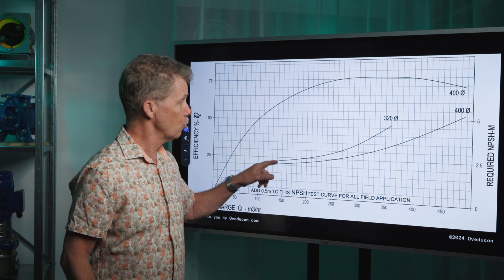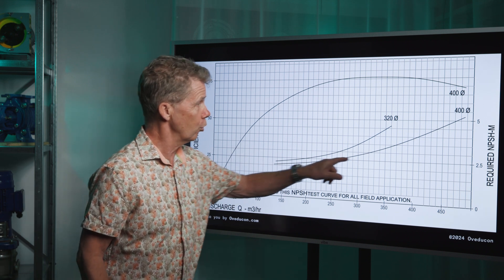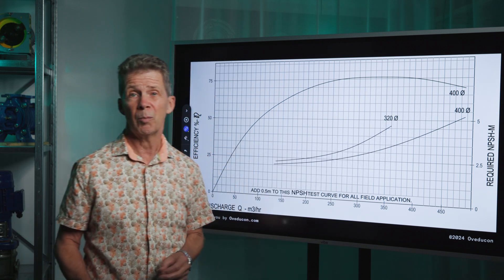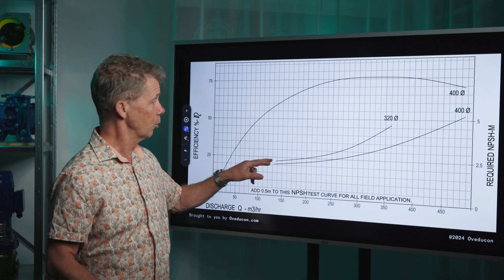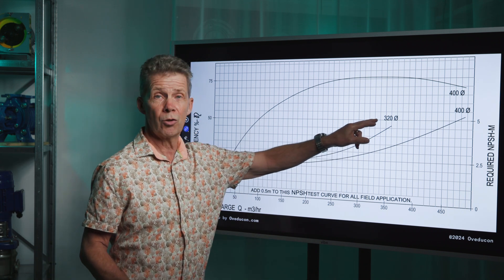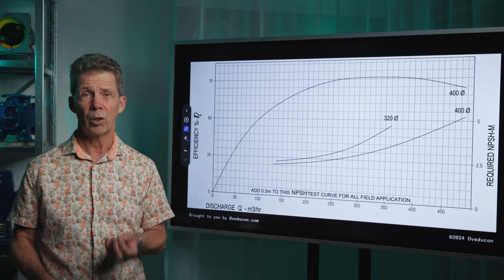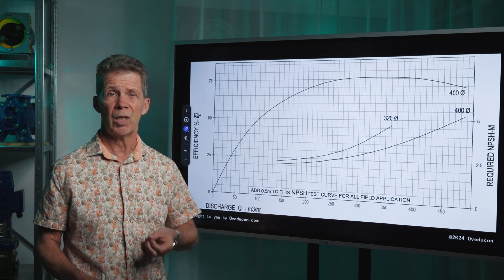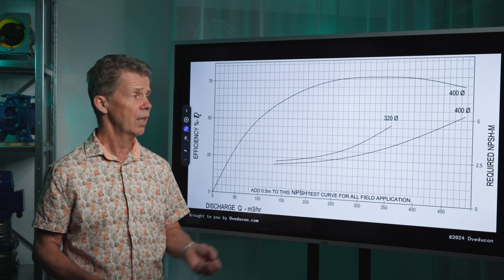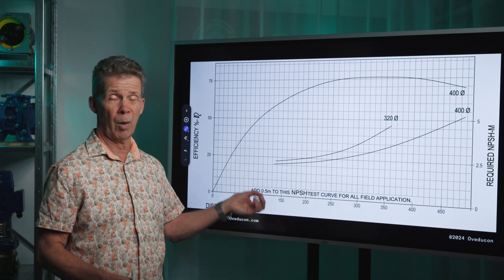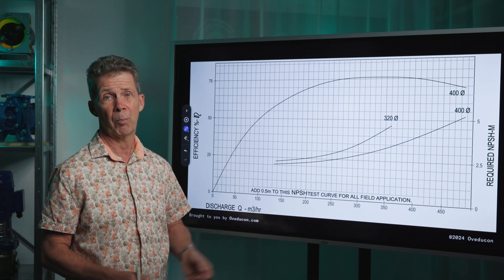In this pump curve you see the NPSH curve of impeller diameter 400 and for an impeller diameter 320. So you don't have to calculate the NPSH-R. NPSH-R is already given in the pump curve made by the pump manufacturer.